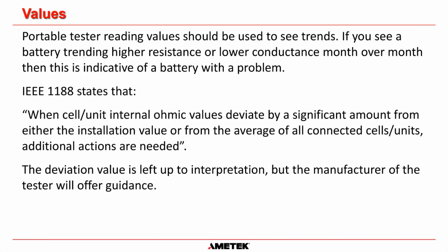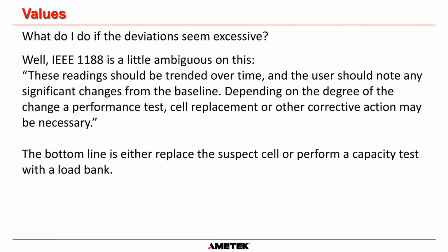There is no official industry standard. It's up to you, and up to how much money you have in the budget. Do you want to do a capacity test? There are so many variables that nobody can create a standard. So what do you do if the deviations seem excessive based on all the information that you have at hand? Once again, IEEE 1188 is a little ambiguous on this. It says that the readings should be trended over time and that the user should note any significant changes from the baseline. Depending on the degree of that change, either a performance test, cell replacement, or some other corrective action may be necessary. Unfortunately, they're not pinning themselves down to something.